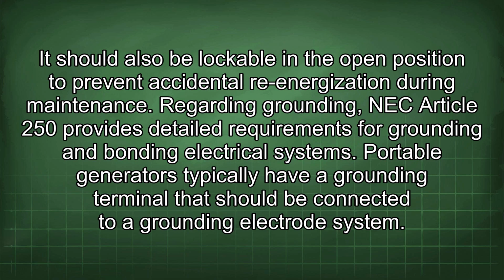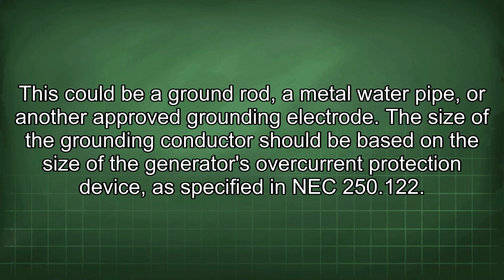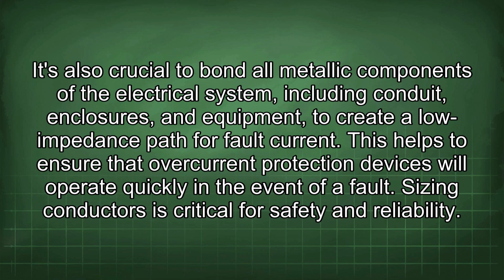Regarding grounding, NEC Article 250 provides detailed requirements for grounding and bonding electrical systems. Portable generators typically have a grounding terminal that should be connected to a grounding electrode system. This could be a ground rod, a metal water pipe, or another approved grounding electrode. The size of the grounding conductor should be based on the size of the generator's overcurrent protection device, as specified in NEC 250.122.